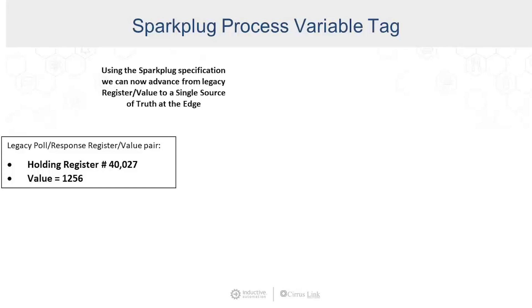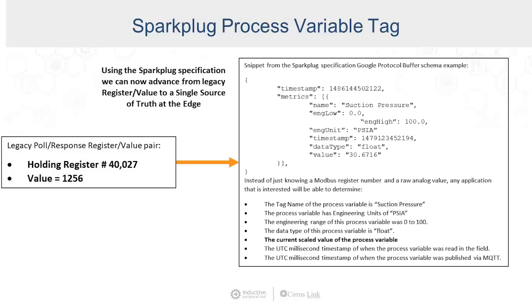But with Sparkplug, we can advance from legacy register value information to a single source of truth at the edge. Taking this same value and representing it from an edge device that implements MQTT Sparkplug, when we subscribe to this tag we actually have a tag name of suction pressure, process variable engineering units of PSIA, an engineering range of 0 to 100, and we know this process variable is a floating point. The current scaled value is published along with a UTC millisecond timestamp of when the process variable was read and published via MQTT.